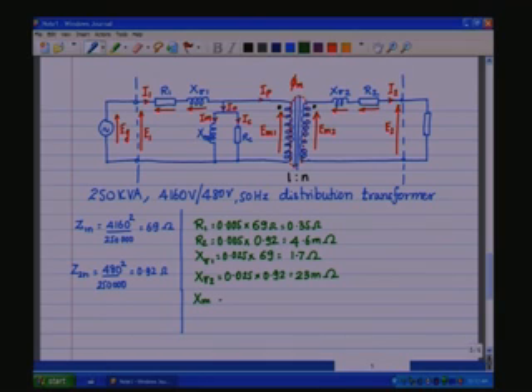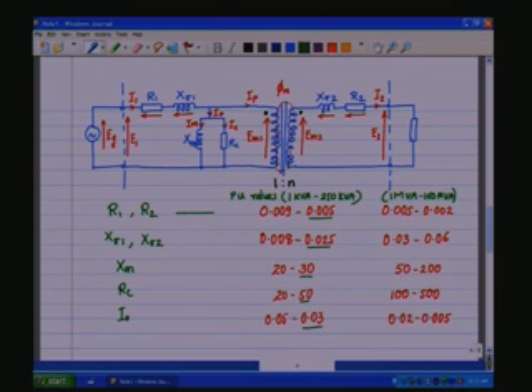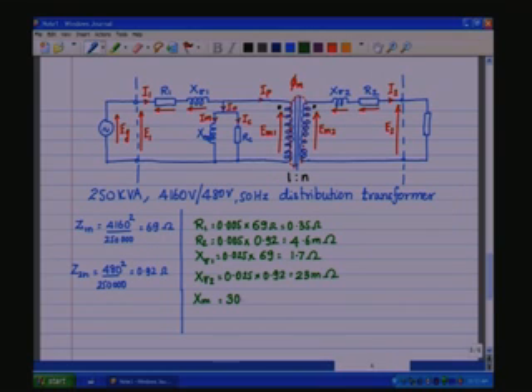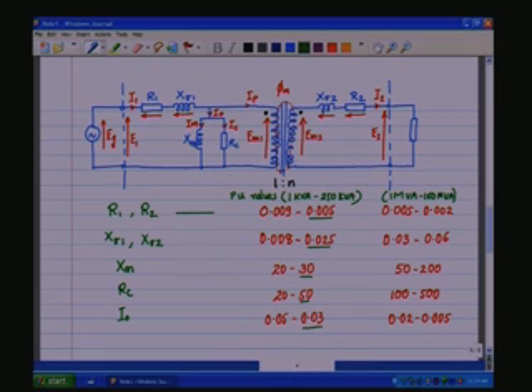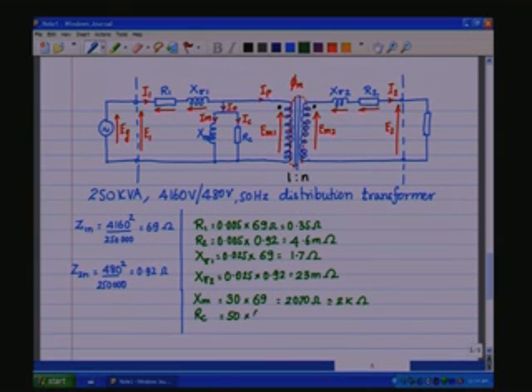Now, XM, the magnetizing reactance. The magnetizing reactance has a per unit value of 30, which is 30 into 69 ohms, the base impedance on the primary side, which gives you 2070 ohms, or roughly about 2 kilo ohms. And RC has a value of 50. So, it is 50 into 69, which is 3450 ohms. It's approximately 3.5 kilo ohms.